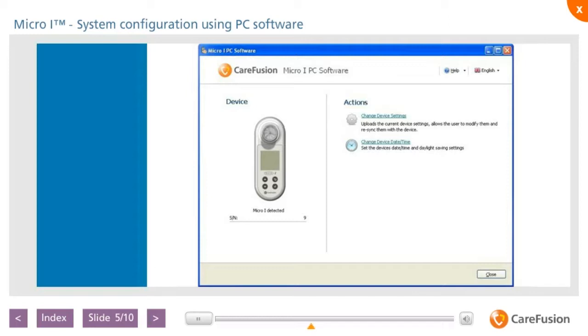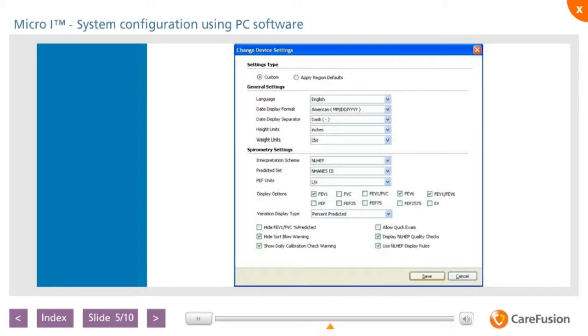The PC software language can be changed by using the drop-down arrow in the right-hand corner and selecting another language. The settings menu allows the language, height and weight units to be altered by using the drop-down arrow and selecting your requirements. A maximum of 4 indices can be selected by clicking in the box next to each index required. Other options allow a prompt for a daily calibration check, a quick examination without predicted values to be enabled or disabled, and also display NLHEP, that's the National Lung Health Education Program, quality grades for the test session.